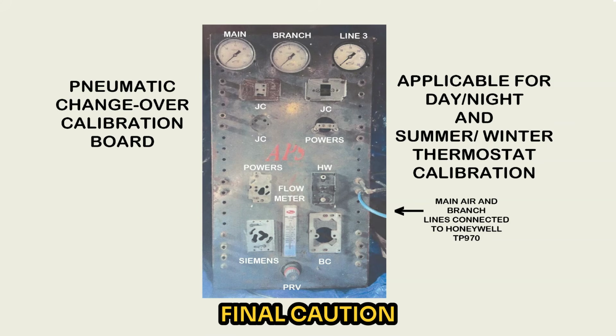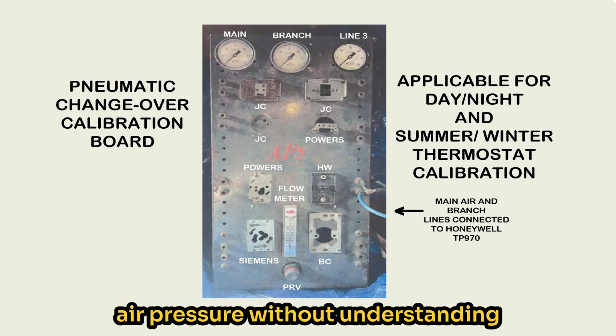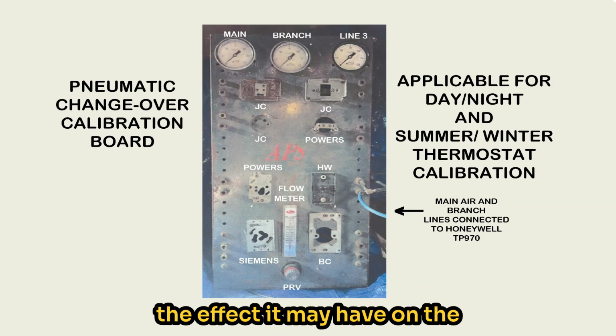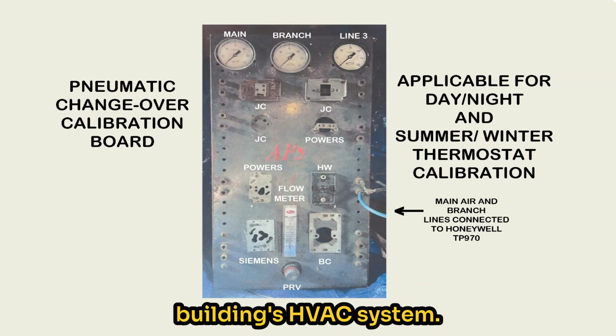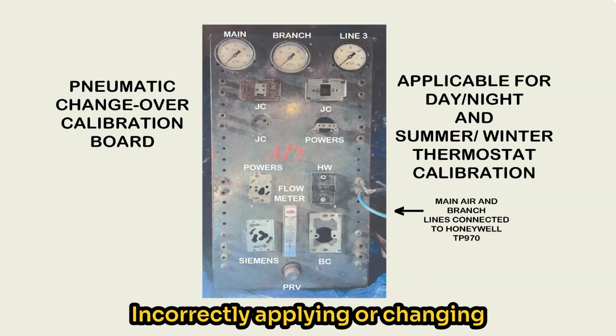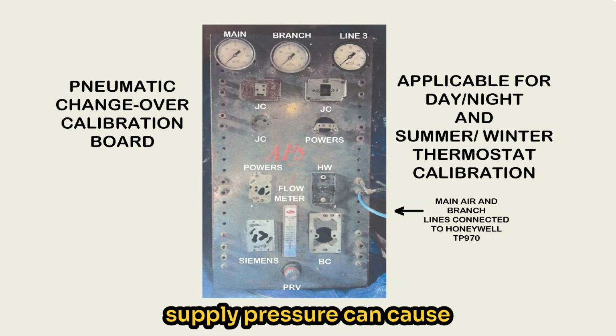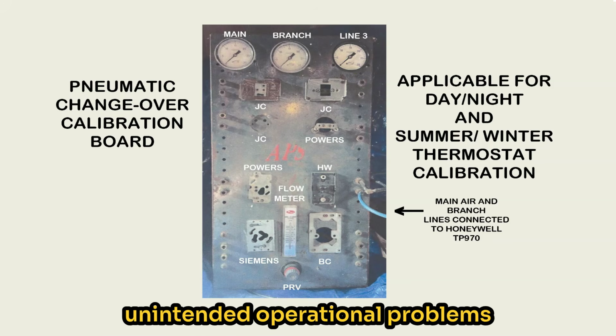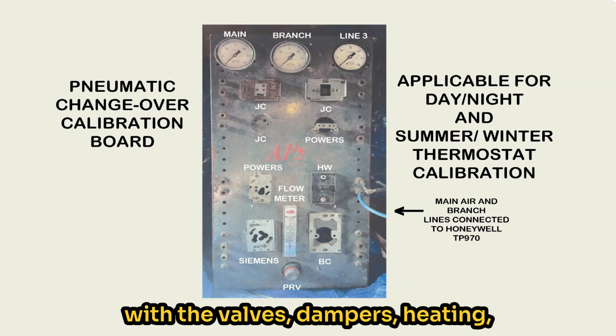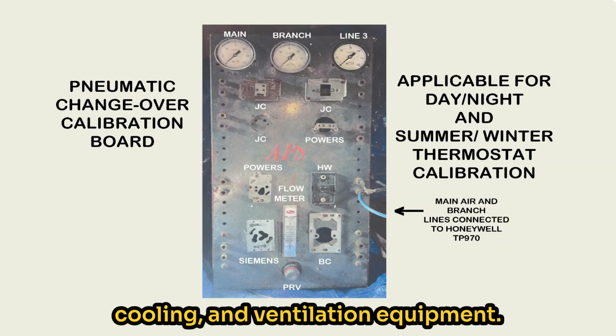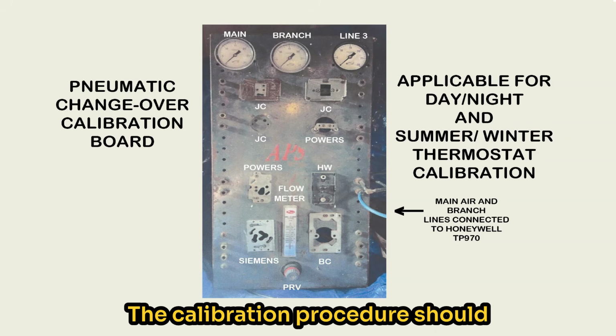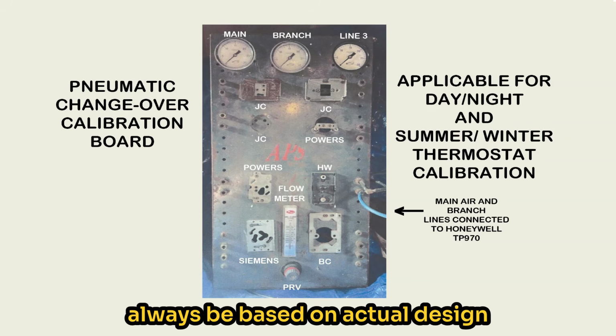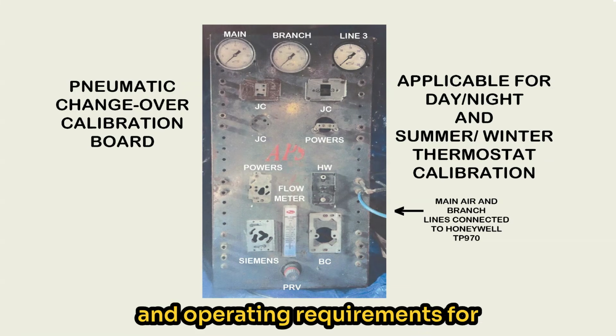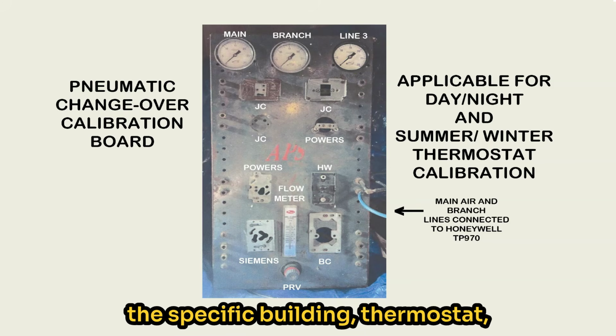Final caution, never change or simulate the main air pressure without understanding the effect it may have on the building's HVAC system. Incorrectly applying or changing supply pressure can cause unintended operational problems with the valves, dampers, heating, cooling, and ventilation equipment.